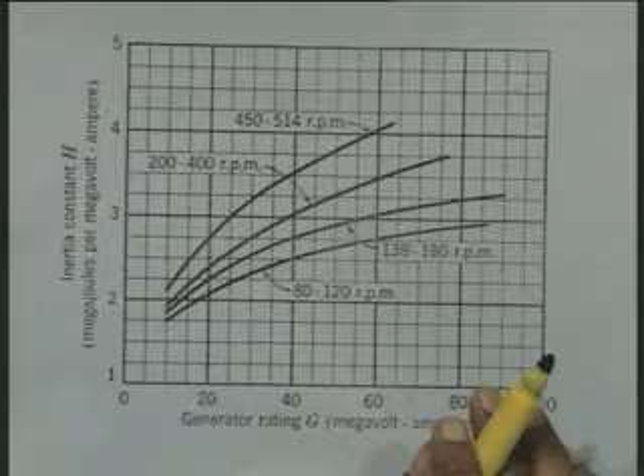Now, I would like to know from you what this inertia constant H is, whether it is the inertia constant of the prime mover, or whether it is the inertia constant of the rotor of the synchronous generator, or it is the inertia constant of the prime mover and rotor put together. Who will reply to this? The question I have posed is about inertia constant H for the synchronous machine: whether it corresponds to the total inertia constant of the turbine plus generator rotor, or only generator rotor, or only turbine. Should be the total. Yes, you are correct. The inertia constant is the total inertia constant of the system, that is, for the rotating body. Okay.